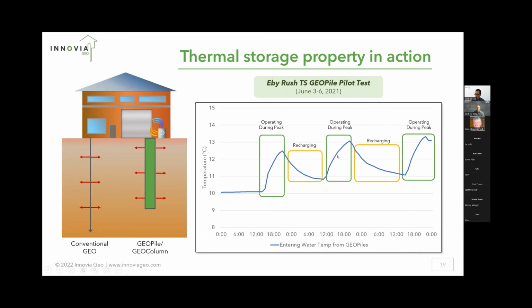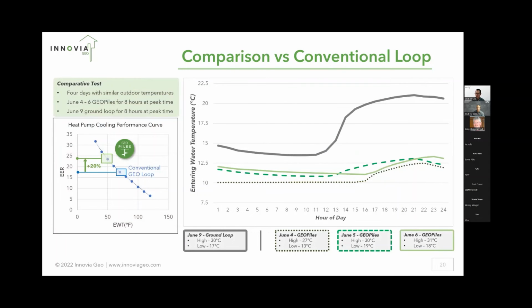And then what we did was the next day, we did the same thing. We turned it on around noon, let it operate for that period of time, and then we see that effect still happening. And so this was a controlled test to test this thermal storage effect, but it has real implications for the efficiency of operation of a system. And so what we ended up doing was a few days later, we did a similar test with the conventional geothermal loop that was installed at the station there. And so here are the results that we have.